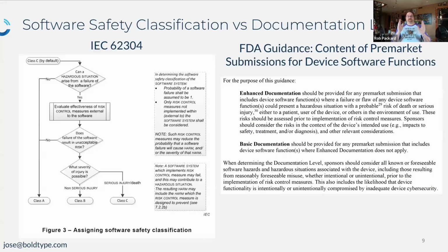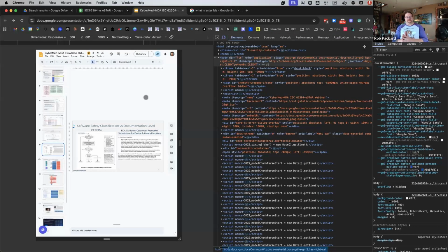I say use a 5-point scale because that's what the FDA is most used to. If you have a 10-point scale, you spend a whole bunch of wasted time arguing over whether it's a 5 or a 6. The smaller the scale, the less arguing goes on. And then I say 3s, 4s, and 5s could be reportable. 1s and 2s are not. Reportable events are something that could result in a serious injury. So if you're saying it's a 3, then you're saying it's a serious injury.